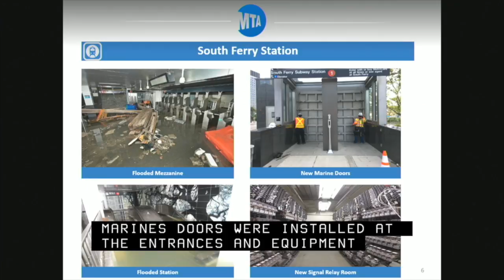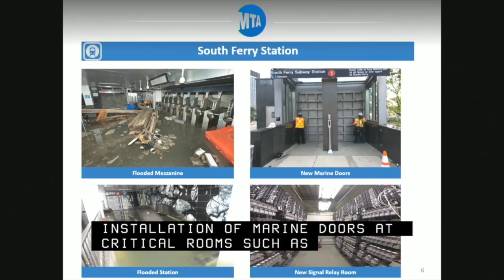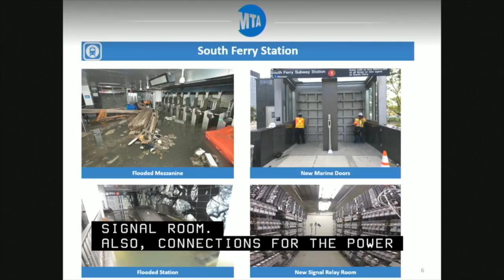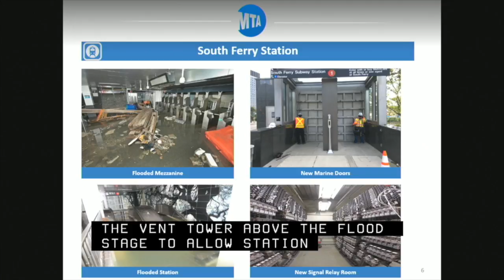A secondary measure of protection included increasing capacity of station pumping and installation of marine doors at critical rooms such as the signal room. Also, connections for a power generator and controls for the pumping system were installed in the vent tower above the flood stage, to allow station pumps to continue working should outside service be lost during a flood event.